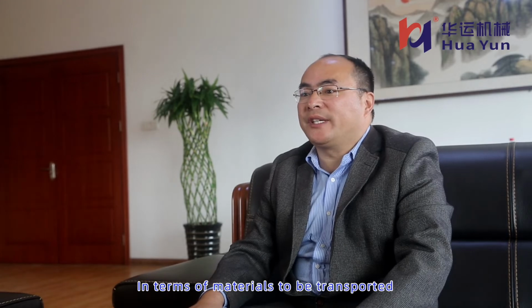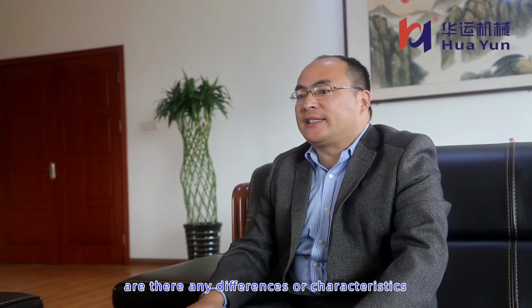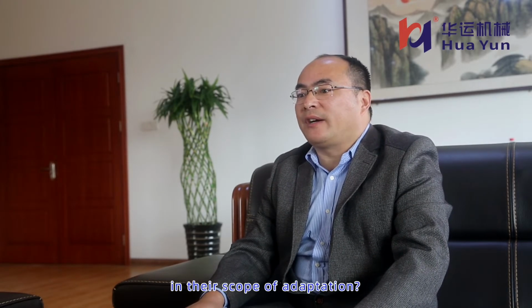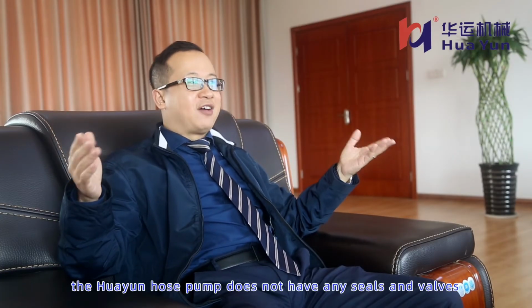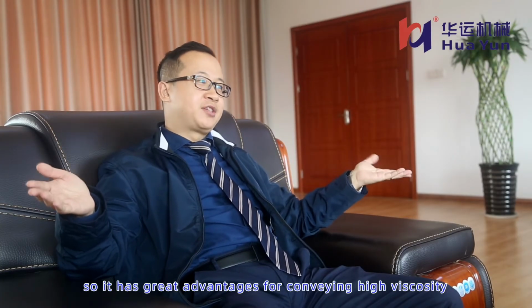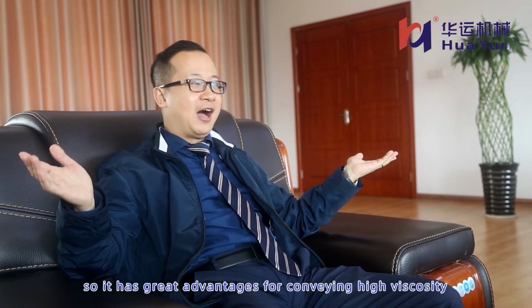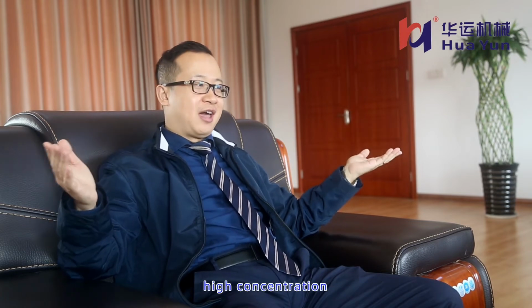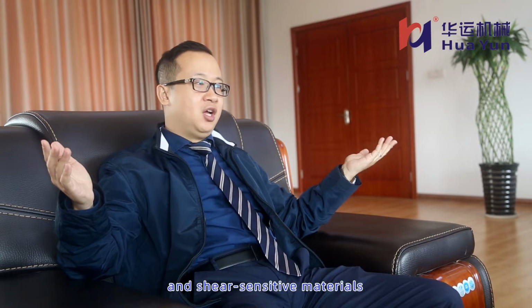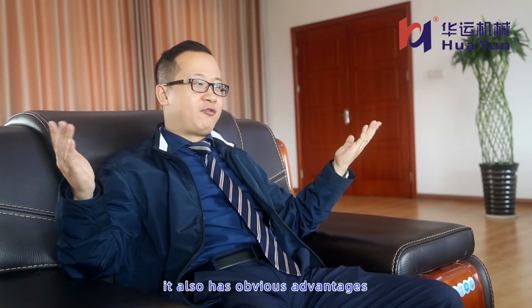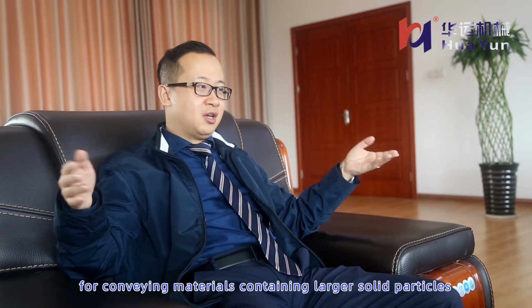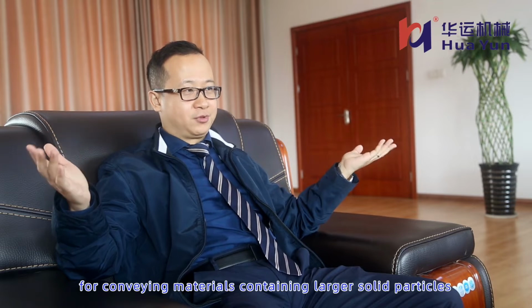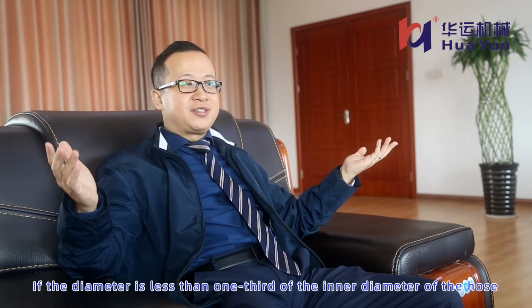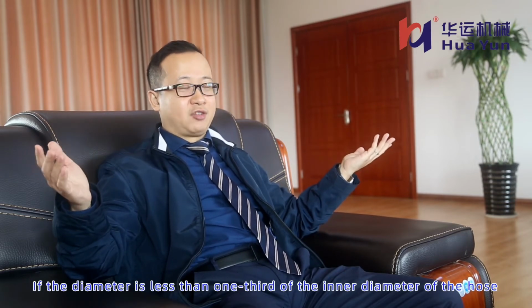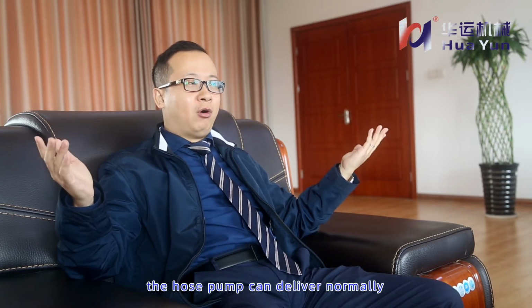In terms of materials to be transported, are there any differences in their scope of adaptation? First of all, the Huayun hose pump does not have any seals or valves, so it has great advantages for conveying high viscosity, high concentration, and shear-sensitive materials. In addition, it also has an obvious advantage for conveying materials containing larger solid particles. If the diameter is less than 1/3 of the inner diameter of the hose, the pump can deliver normally.